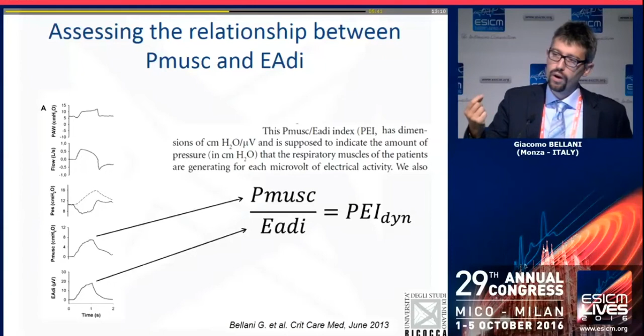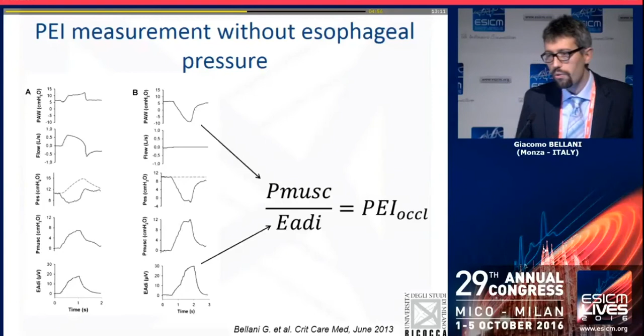How do you compute it? It's very easy. You just push an expiratory hold button. The patient will make an effort. At this stage, the Pmusc, the pressure generated by the muscles, is translated directly on the airway. So you measure it as an airway pressure swing. And simultaneously, you have the EDI swing. So the ratio between these two will let you know how much pressure the patient was able to generate by this given EDI. And so you can then apply this factor to the subsequent breathing to know how much pressure the patient is putting on the respiratory system.